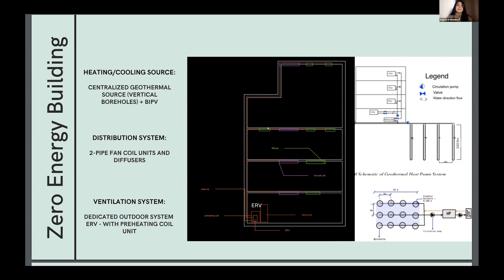As for the ventilation system, a dedicated outdoor air system will be drawn to an ERV unit, equipped also with a preheating coil that will temper the outside fresh air supplied. All of this equipment was sized and chosen to optimize energy consumption while complying with the constraints we faced in this building, and to do so, we performed many simulations, such as an HAP simulation.